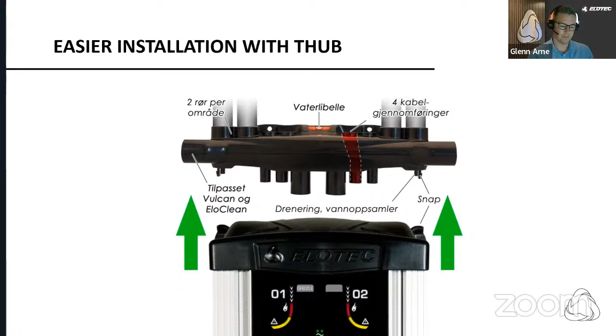There is a lot of dust and a lot of workers inside the building, and instead of damaging the aspiration detector before commissioning, you can just mount the pipes and the T-hub. When doing the commissioning, you can easily snap it on and mount the Elotec Aspect detector. Then it won't get contaminated with dust during the building process. So we recommend using the T-hub in every installation.